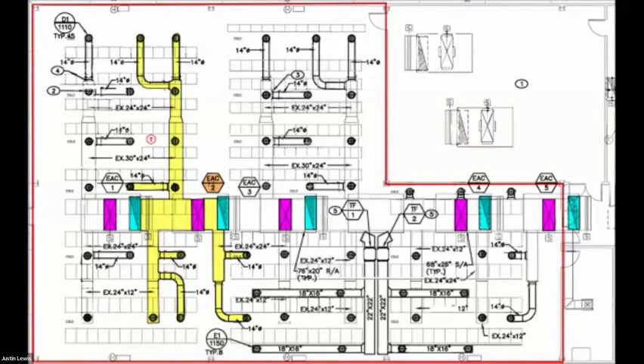Long story short, we were able to resolve the issue by adjusting the satisfied mode speed to approximately 25% fan speed. We worked with the manufacturer's rep to get that adjusted. At that point, the back pressure from the other systems essentially deadheaded the airflow. They ended up not needing to replace the units. This was a sequence issue, not an equipment issue. So this saved them a lot of money.